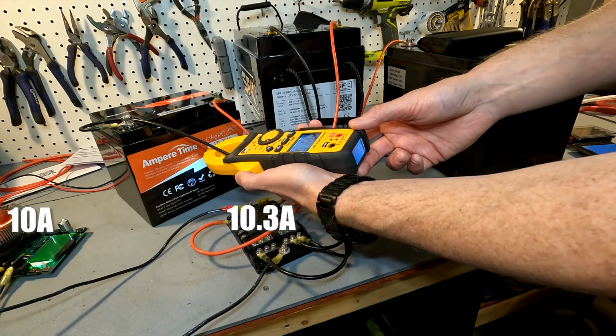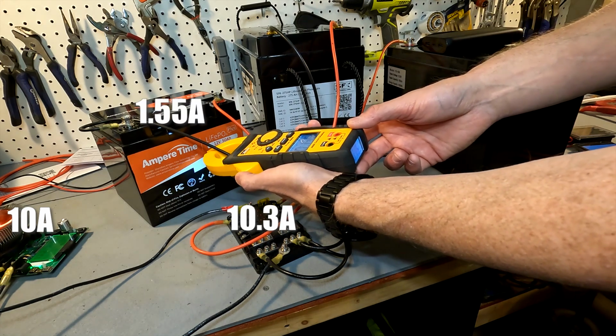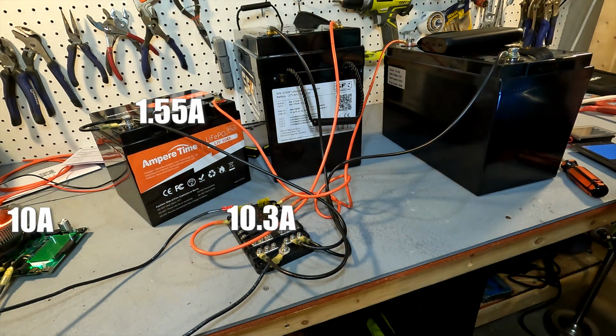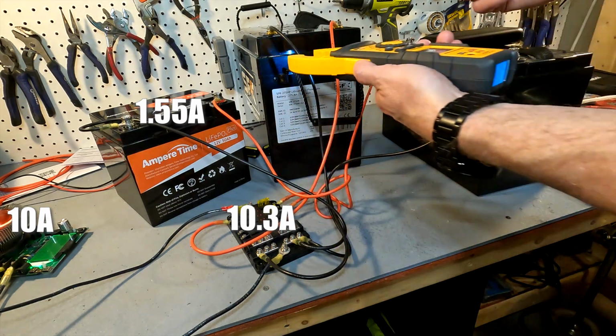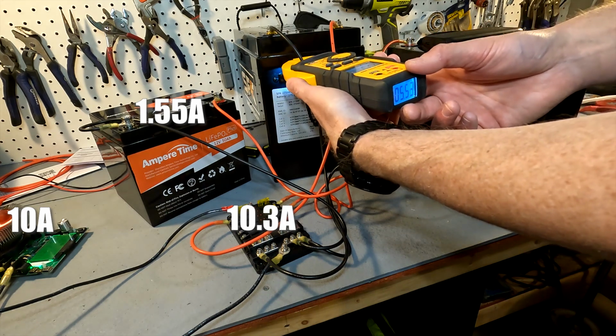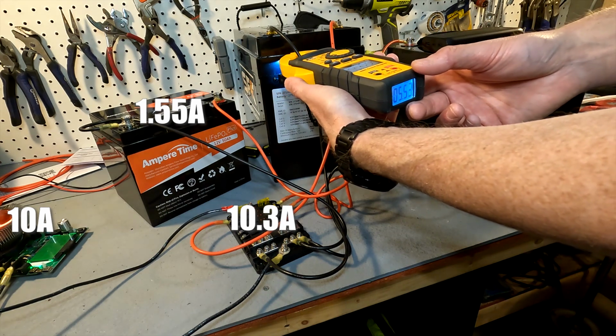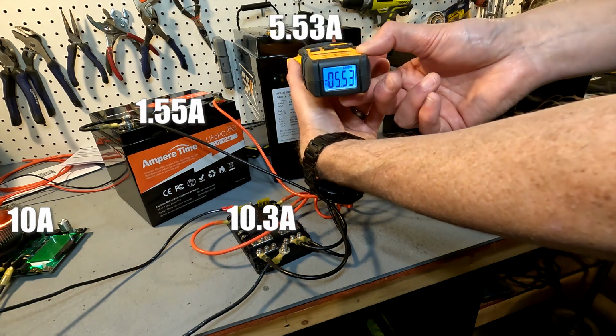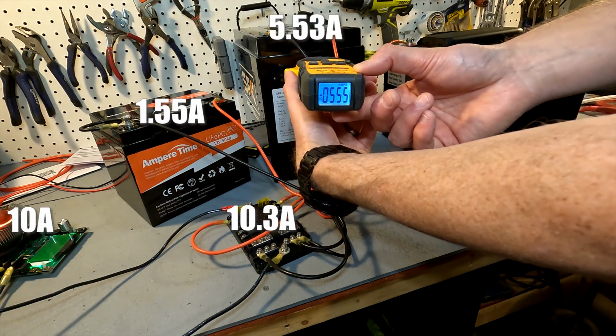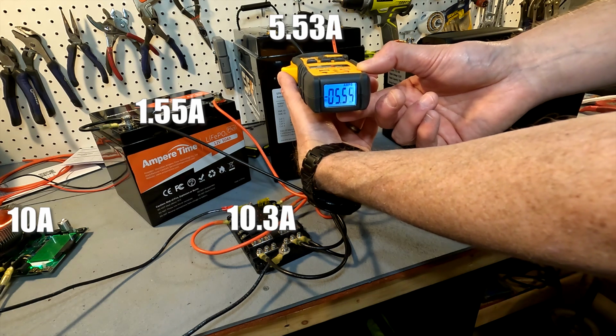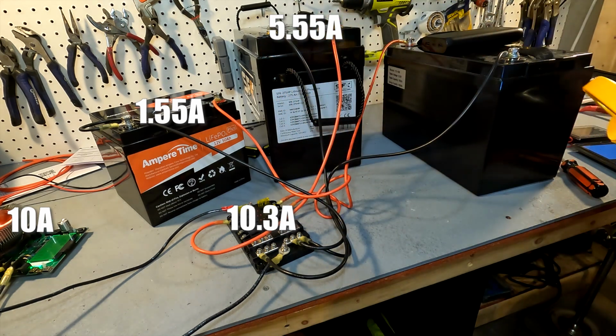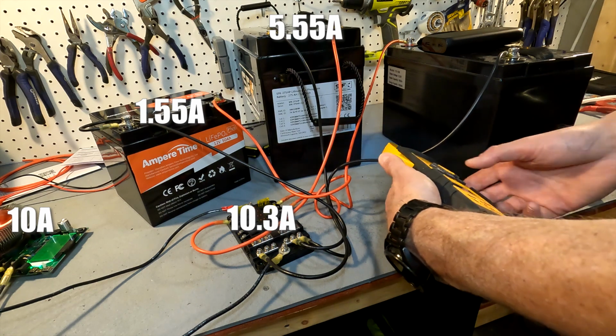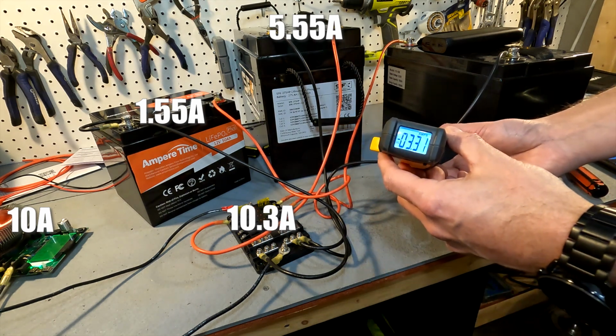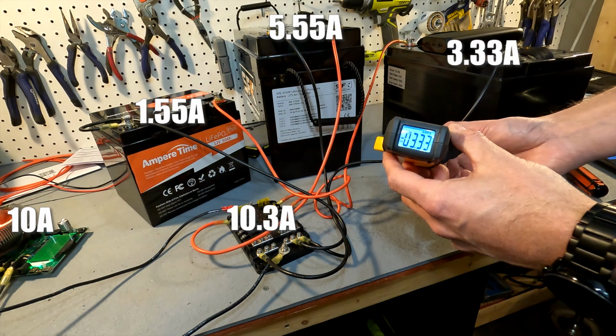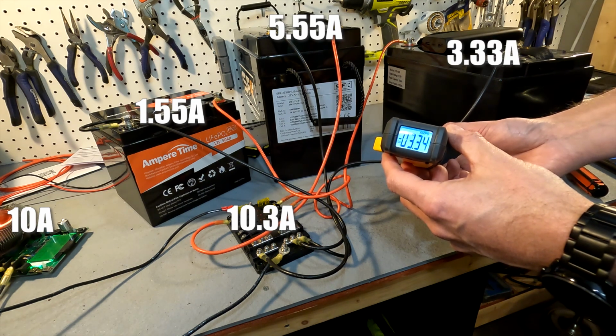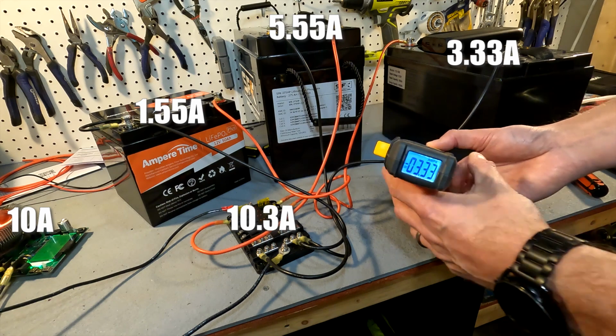What I have is 1.55 amps from the 50 amp battery. And from the 275 amp hour battery, we're pulling 5.53, we'll say 5.55. If my calculations are correct, this should be right around 3 amps. Yep, 3.33 amps from this one.